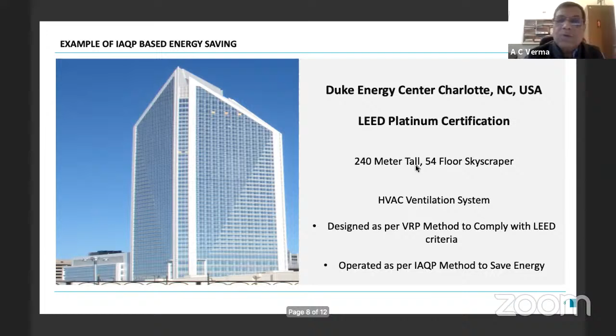They designed it based on the minimum air requirement using the VRP method, and also designed it based on the IAQP method. The VRP method helped them get the LEED Platinum certification, and the IAQP method helped them reduce their energy cost. This hybrid method has been used very successfully, and this building has been operating for a long time, as it is one of the headquarters of the Duke Energy Center.